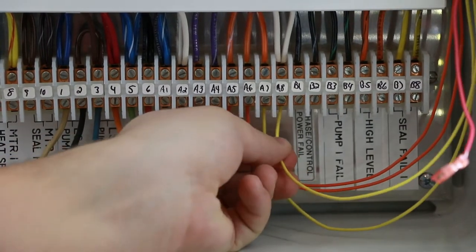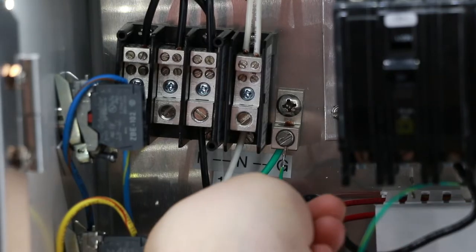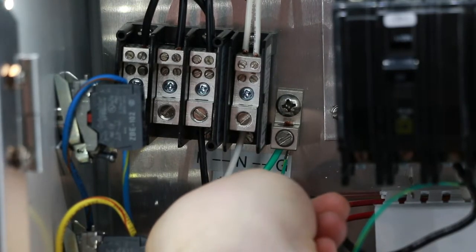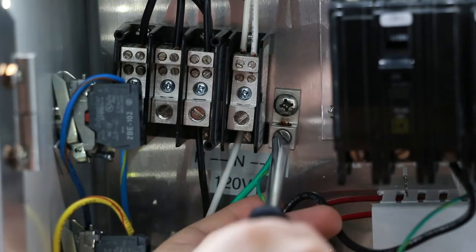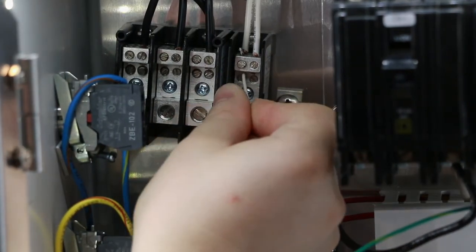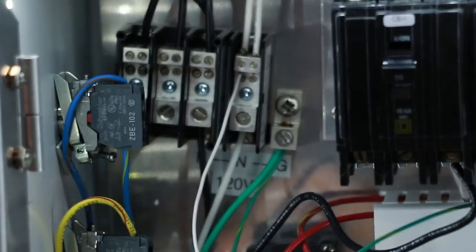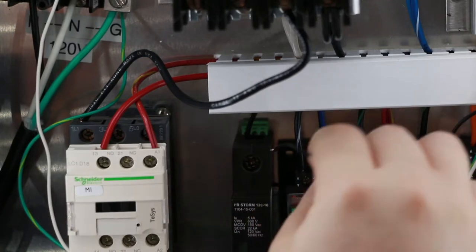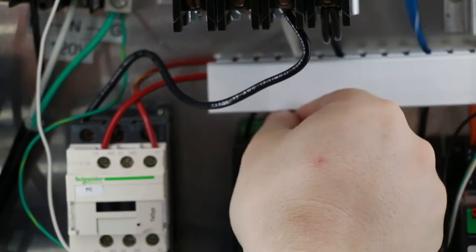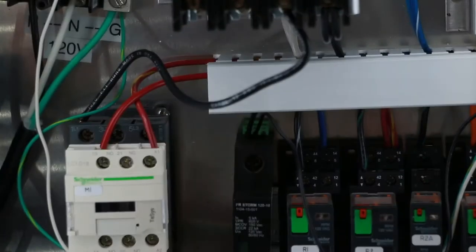The two yellow alarm leads should be connected to a powered contact. Now, land the green wire on your panel ground. Land the white wire on the panel neutral, and the black lead on your 120-volt source. Here, I'm using the lightning arrestor to protect my OmniBeacon from voltage spikes.